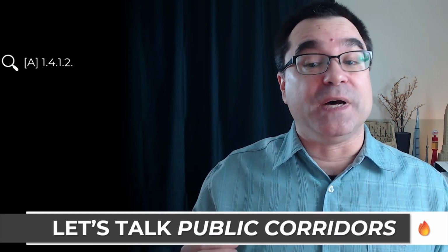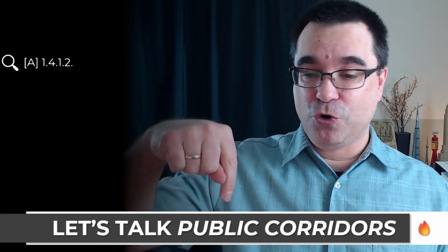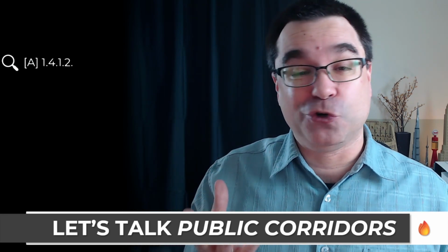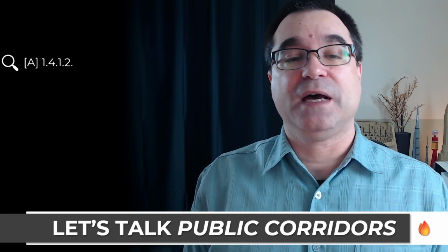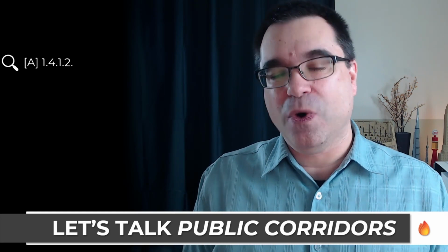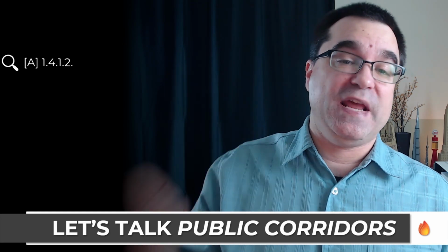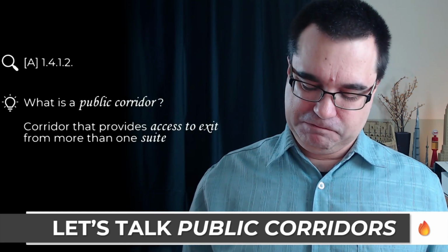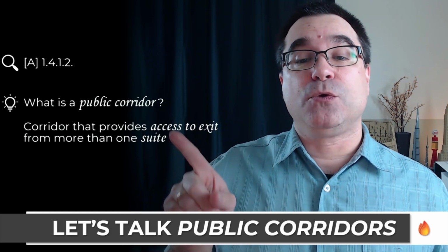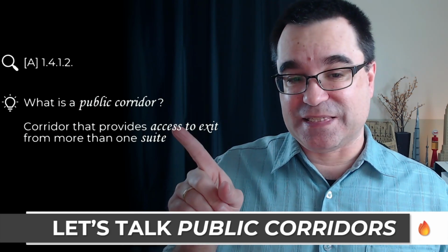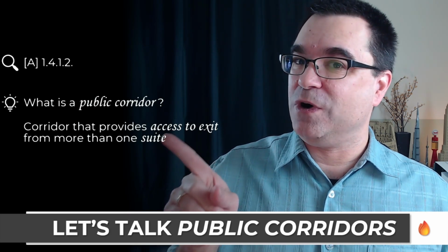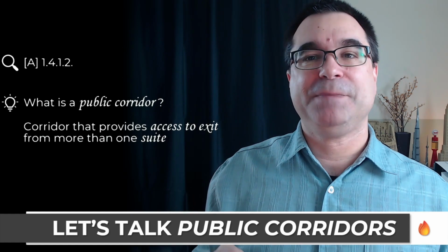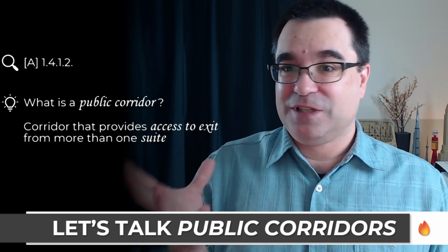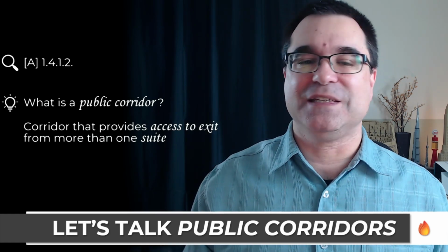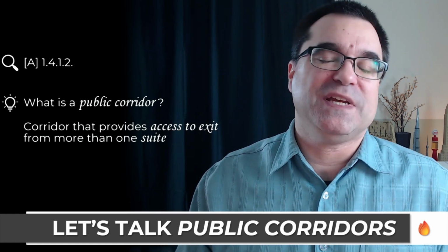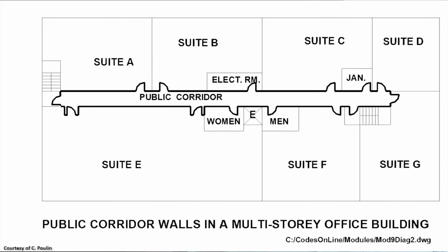Now let's talk about public corridors. Public corridors, again, is a defined term in the Ontario Building Code. So you'll find a definition under Article 1.4.1.2 under Division A. Public corridors are corridors that provide access to exits for more than one suite. Okay, so this is important. If more than one suite share this corridor to get them to an exit, it's called a public corridor. It's a shared corridor.